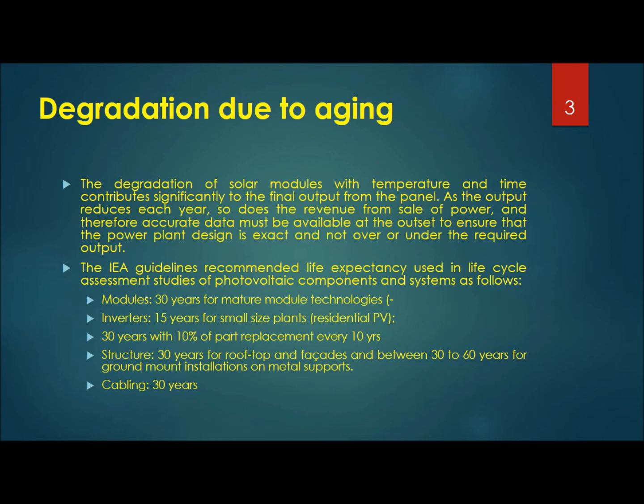The effect of degradation of photovoltaic modules and arrays and their subsequent loss of performance has a serious impact on the total energy generation. And the maximum power at standard test conditions is the most critical characteristic of the photovoltaic module or array for all of its operational life. For calculation of the system size and the associated investment cost, Pmax is the key working value.